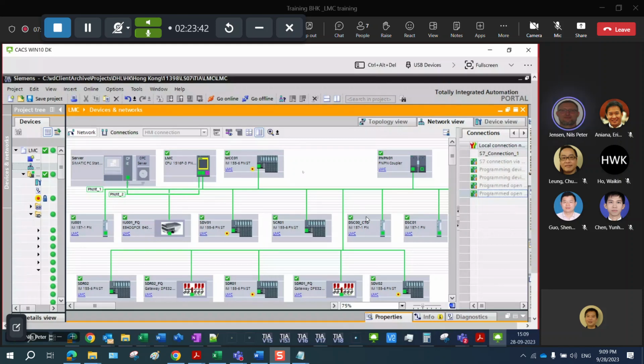It took us 2 to 3 days to diagnose the problem. The last thing we did was electrically check by disconnecting half of the sorter loops from the other loop, then check the continuity from one side to the next. After doing that, we identified this side, because the sorter chain resistance—you cannot always get a fixed value. There will always be a resistance, but if you're using a digital meter, you have to make sure the reading is stable.